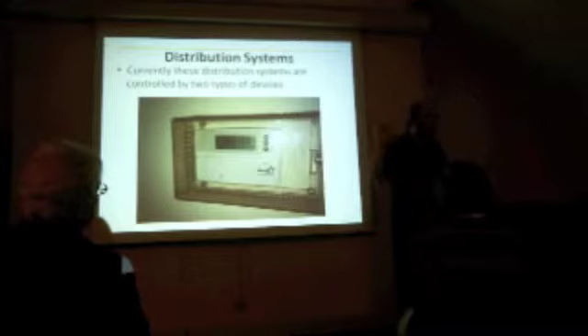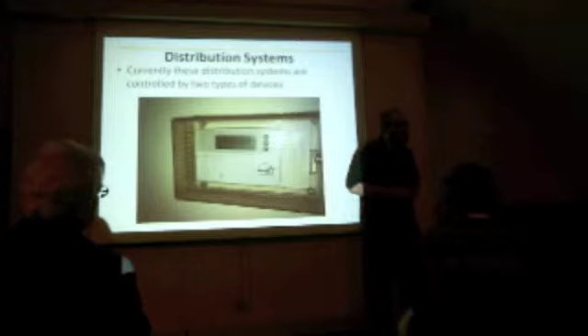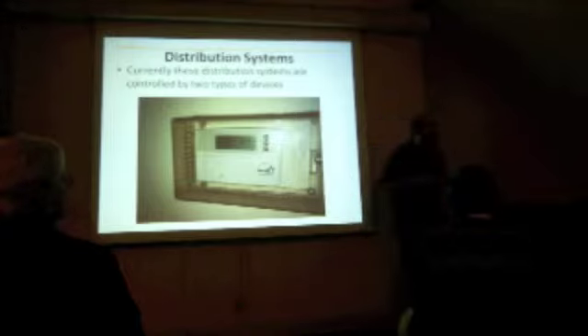It really depends on the type of heating source that you have. For the kind of natural gas boilers that you have here, that are quite big compared to your heating load, it is more efficient to turn them down at night. The basic way that works is that the rate at which heat is going to leak out of your building depends on the delta T, the temperature difference across the wall. And so the extra heat you need when you pump it back in is generally offset. There are a few things, depending on how you're moving heat with, say, a ground source heat pump, those you don't necessarily want to set back at night to the same extent.